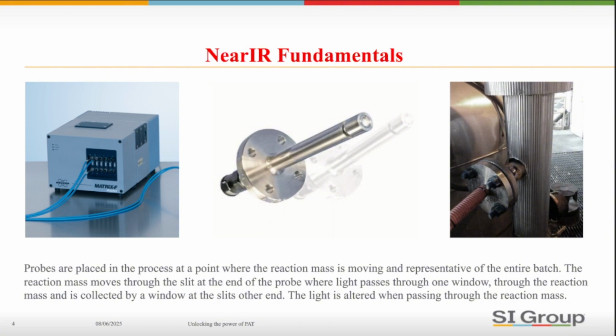The chemical being analyzed flows through the slit. Light is transmitted through one of the windows, through the chemical, and back into the window on the other side of the slit, then returns to the instrument. It is the change of light passing back through the fiber optic cable that the instrument analyzes.